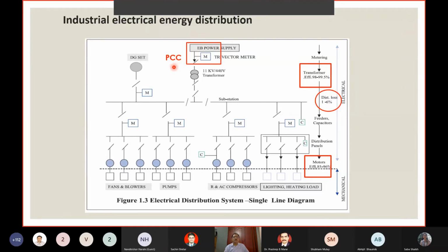Standards like IEEE 519/2014 very clearly talk about the point of common coupling as being the place where the standard is applicable. The standard is not applicable elsewhere in the distribution network. It is applicable only at the point of common coupling. So we have a transformer, we have breakers, then we have a 440 volt bus in which various motors are tied, and as you can notice, they are coupled with fans, blowers, pumps, compressors, lighting, heating loads and so forth. These are the end-use loads.